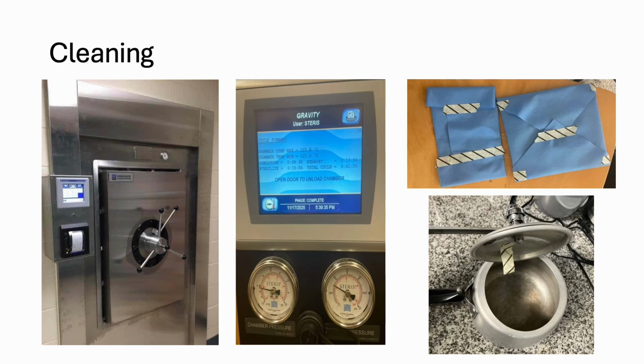So now that you've seen our prototype, you might be curious about how we actually keep it clean. In most clinical settings, they typically use an autoclave, which sterilizes equipment with specific heat and pressure. Our prototype can handle multiple autoclaves just fine. But in lower resource areas, people might just use boiling water. We tested that too, and the prototype held up perfectly after being boiled. We even tried using a pressure cooker as sort of a makeshift autoclave, and as you can see in this image, both the autoclave and the pressure cooker reach the same pressure and temperature needed to sterilize it.